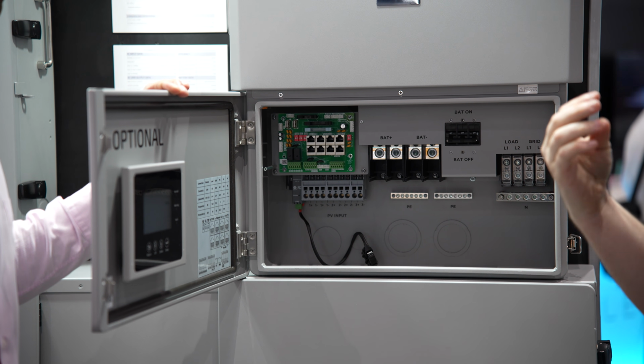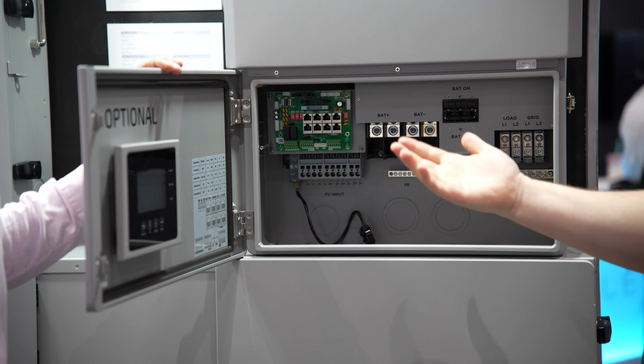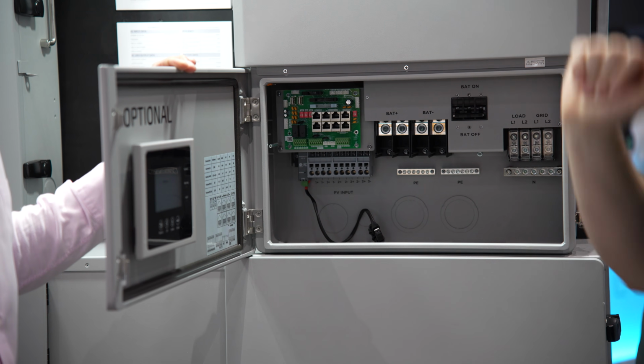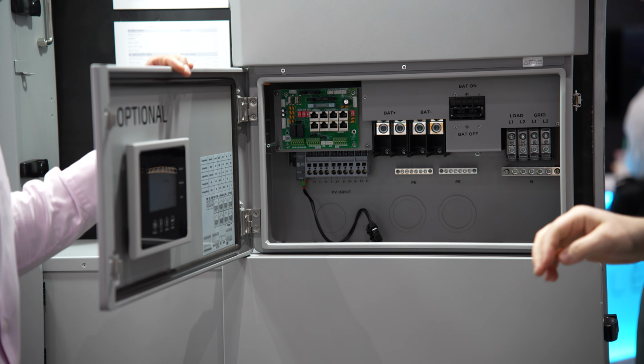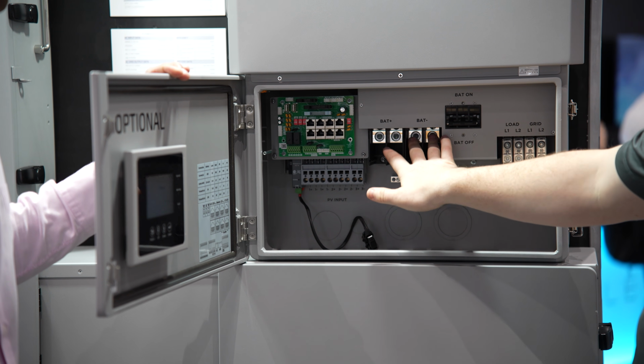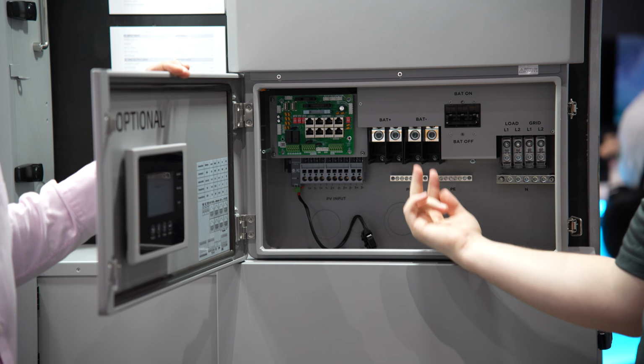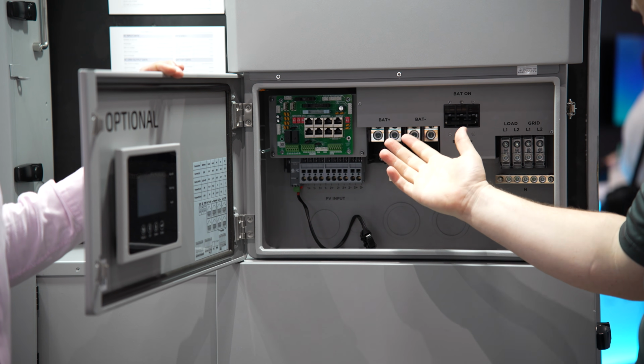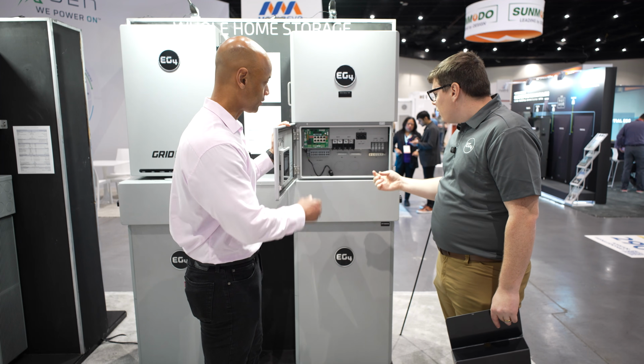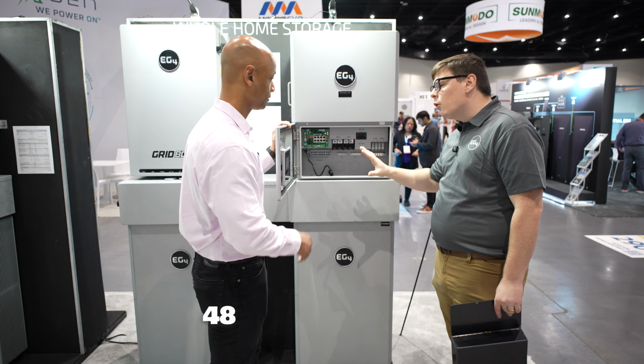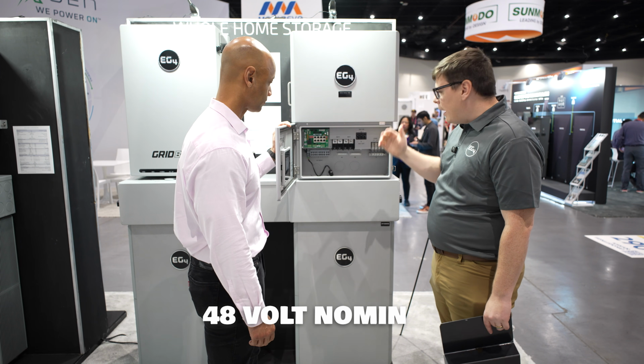It's going to use a number 6 or a number 4, depending on length, copper cable going back to that one breaker. We've got double battery terminals, they're parallel, so you don't need a combiner plate. It's a 250 amp input. And this is all 48 volt nominal, with a peak of about 58.